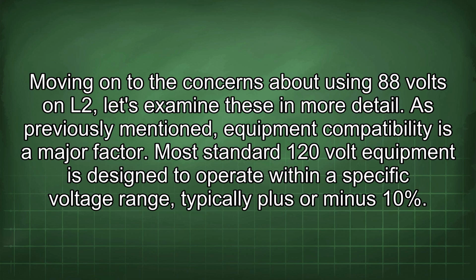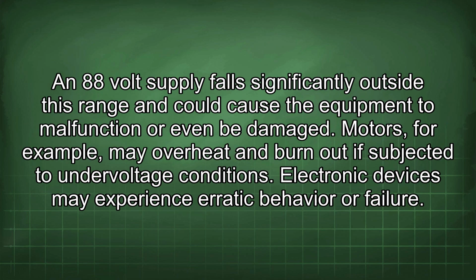Moving on to the concerns about using 88 volts on L2, let's examine these in more detail. As previously mentioned, equipment compatibility is a major factor. Most standard 120 volt equipment is designed to operate within a specific voltage range, typically plus or minus 10%. An 88 volt supply falls significantly outside this range and could cause the equipment to malfunction or even be damaged.